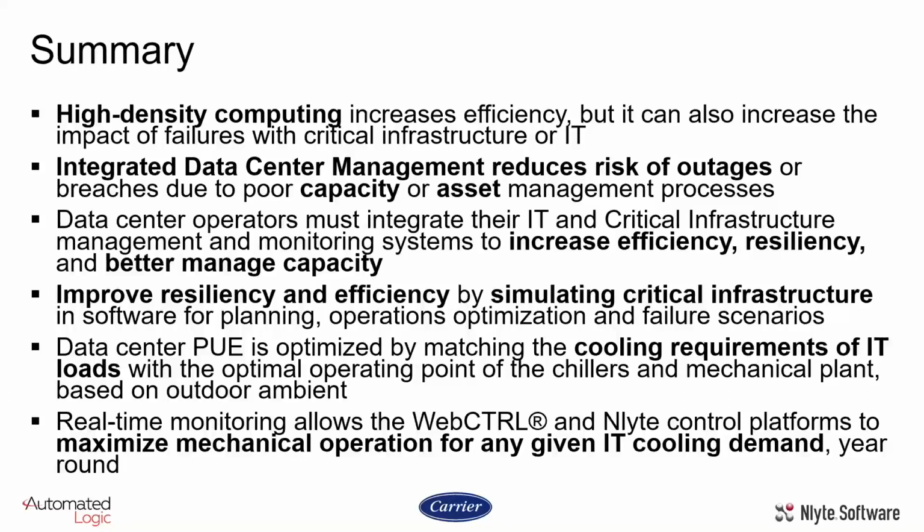Probably many of you have heard of that, and being able to effectively digitally represent your physical environment to plan for all of these scenarios is a key item, and is something that as you get closer and closer to your goals, the gains are harder to achieve without planning tools like that. Data center PUE is optimized by matching the cooling requirements of IT loads with the optimal operating point of the chillers and mechanical plant based on outdoor ambient. And real-time monitoring allows the WebCTRL and Nlyte control platforms to maximize mechanical operation for any given IT cooling demand year-round.